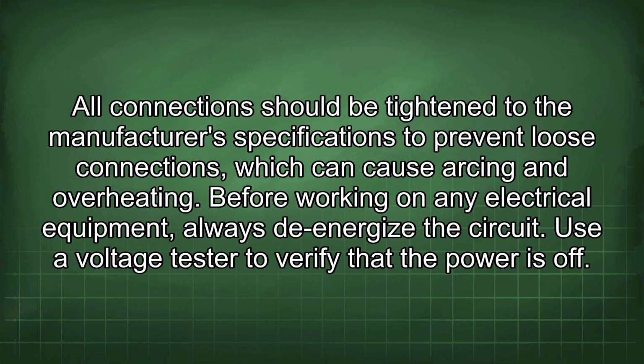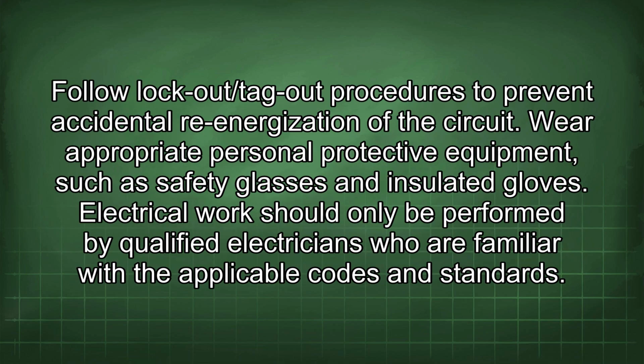All connections should be tightened to the manufacturer's specifications to prevent loose connections, which can cause arcing and overheating. Before working on any electrical equipment, always de-energize the circuit. Use a voltage tester to verify that the power is off. Follow lockout/tagout procedures to prevent accidental re-energization of the circuit. Wear appropriate personal protective equipment, such as safety glasses and insulated gloves.